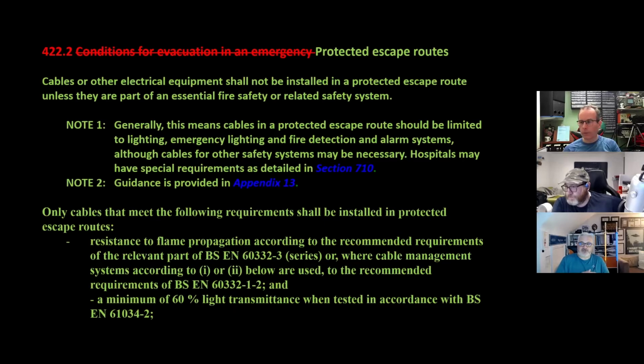Is it me, or is this just going to basically mean LSZH? And by the way, notes 1 and 2 cover conduit systems classified as non-flame propagating, cable trunking and cable ducting systems classified as non-flame propagating, or cable tray and ladder systems classified as non-flame propagating, and power track. Non-fire resistant cables need to satisfy the requirements of the construction product directives.